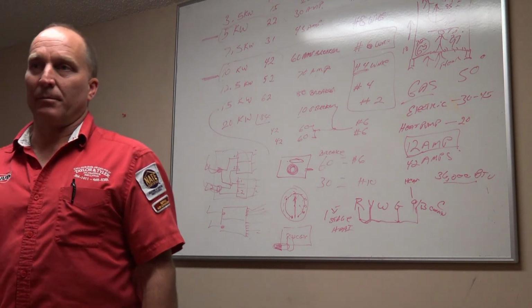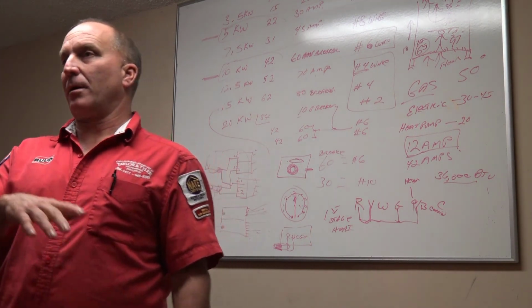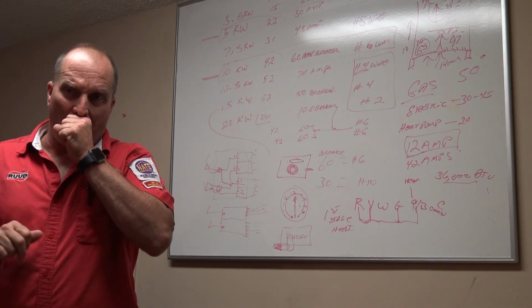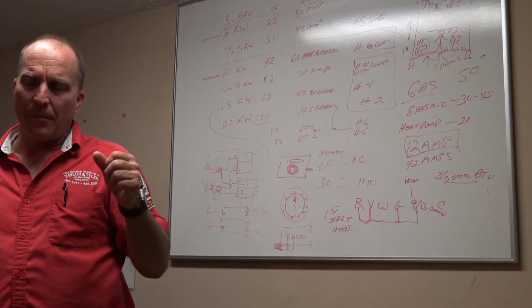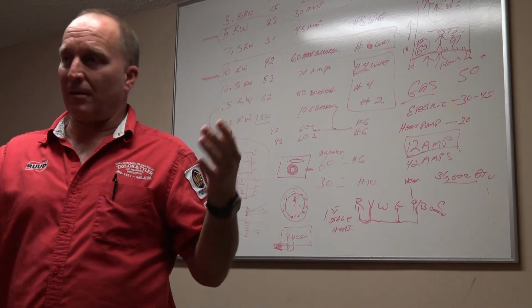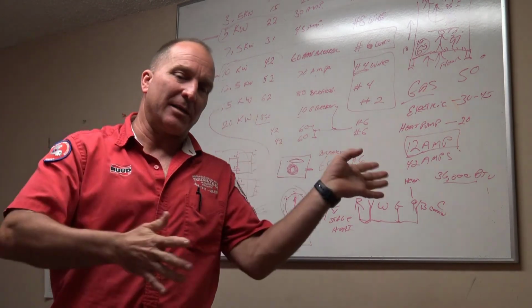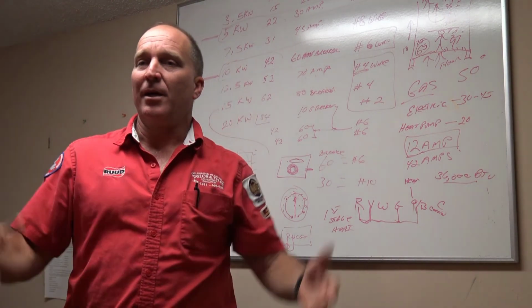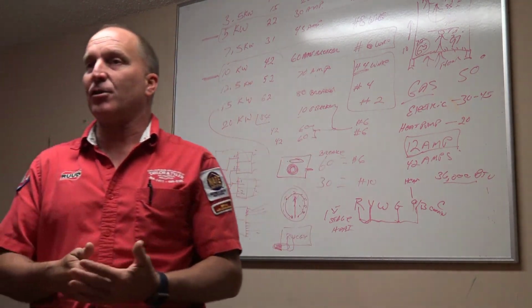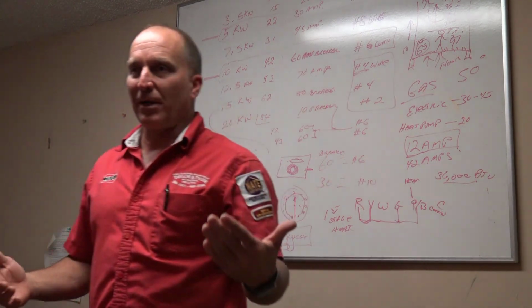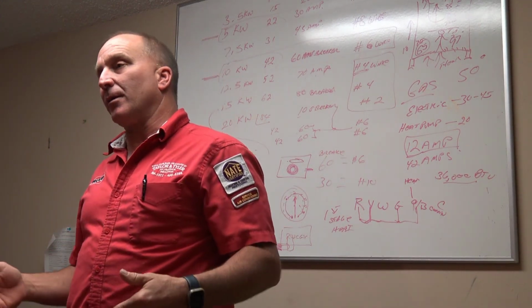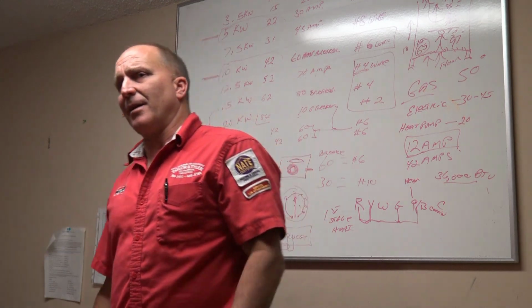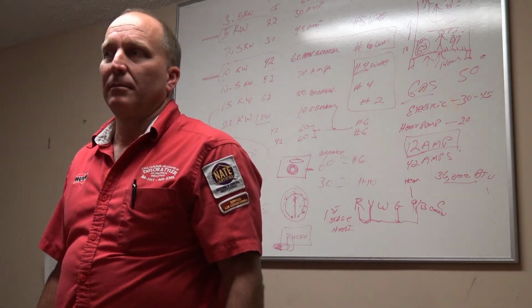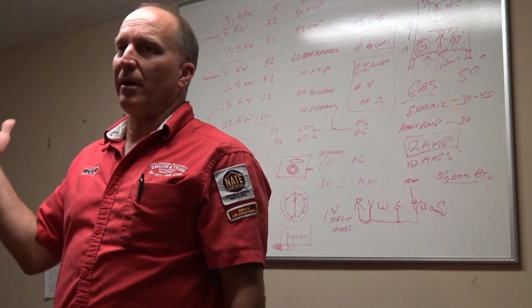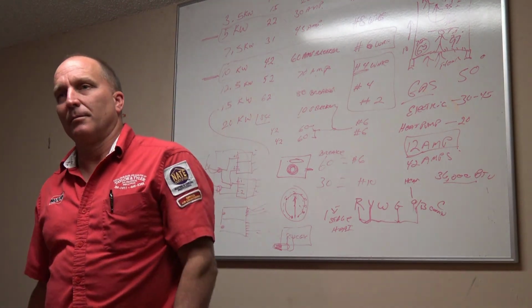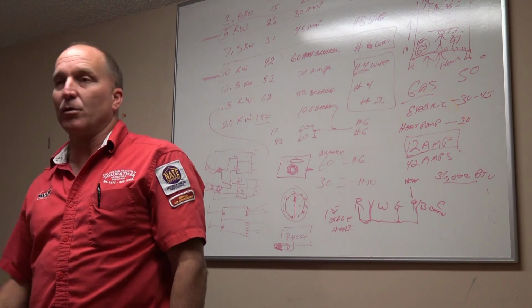Every picture. Supply plenum wrong, or supply plenum missized, and whoever put it in has transitions and duct board blocks off, all that kind of crap. You're taking a picture of it because you want a recommendation to replace that supply plenum. So I have a picture of it. The customer calls me back 2 weeks later and says, your guy said I need a new supply plenum. Well, let me go look. Yeah, I got a picture of it right here. Yes, ma'am, now I can explain to you why you need a new supply plenum.